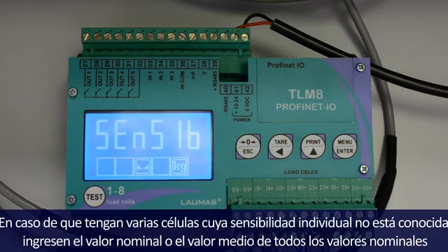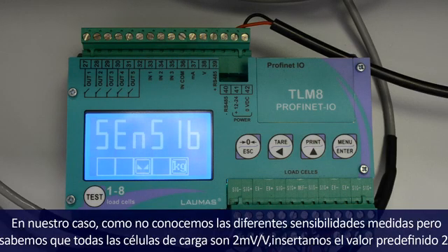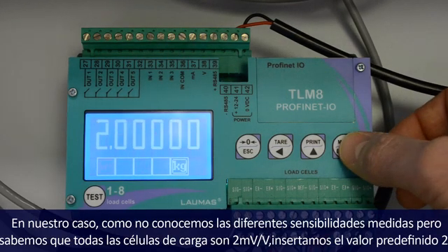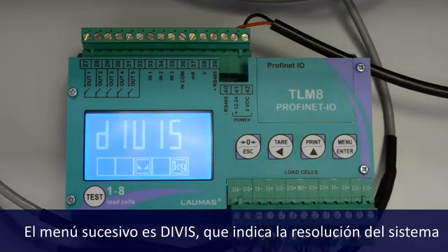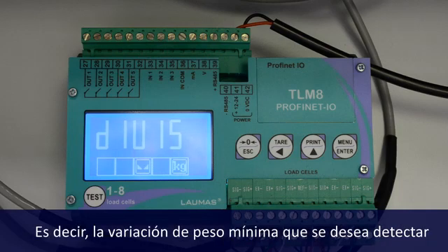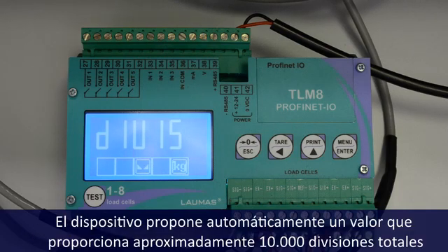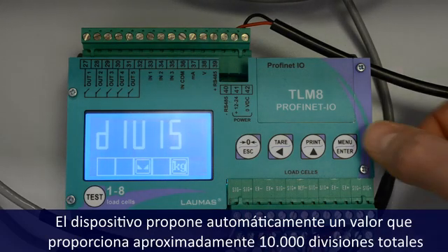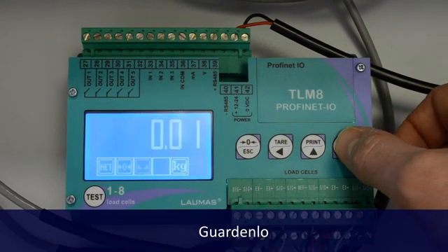If you don't know the measured sensitivity, type here the nominal value, or the average of the nominal values if you have more than one load cell. In this case, I don't know the measured sensitivities, but I know that all the load cells are 2 millivolt over volt ones, so I will leave here 2, the default value. Next is DIVIS, which is the system's resolution, the minimum weight variation you want to appreciate. The device automatically proposes a value which gives you around 10,000 total divisions. We will keep it.